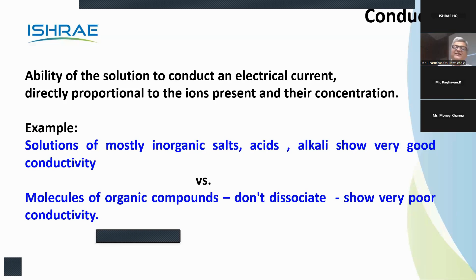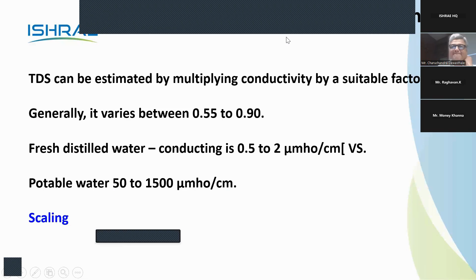So what we do is we take the conductivity reading and multiply it by a fixed number. This fixed number is the thing. 0.55 to 0.90. This number we multiply, and this is how the TDS can be calculated. Fresh distilled water conductivity will be 0.5 to 2 micromhos per cm, whereas potable water will be very conductive water. But ultimately, conductivity is directly connected to TDS, so it is directly connected to scaling.